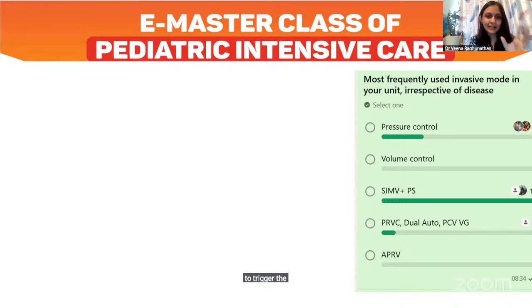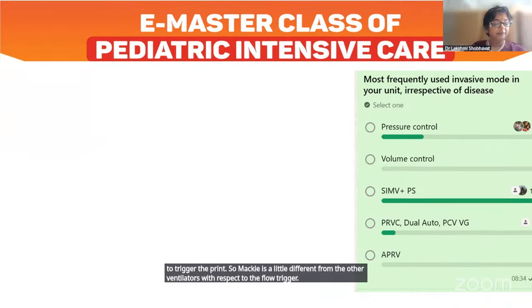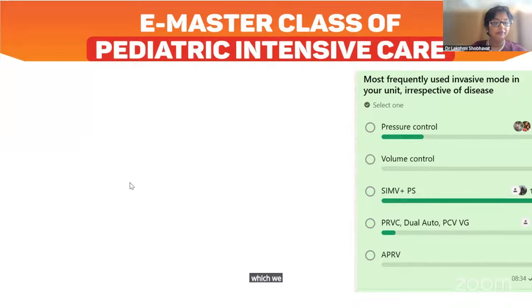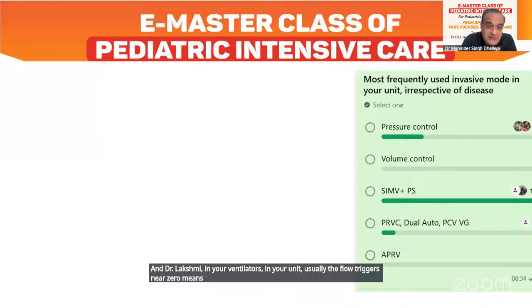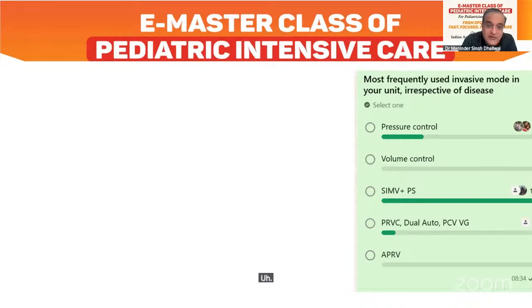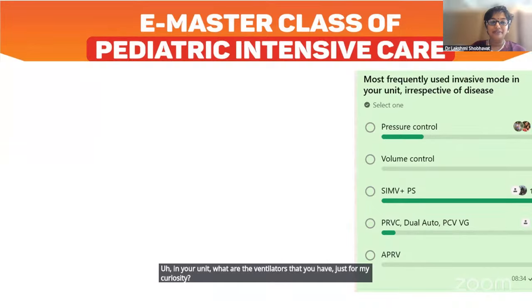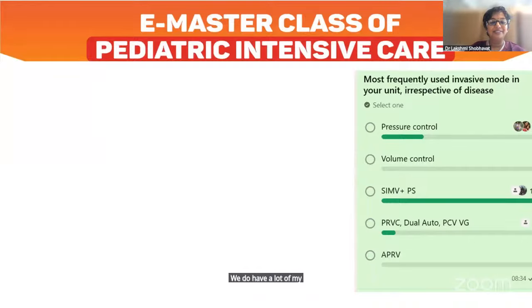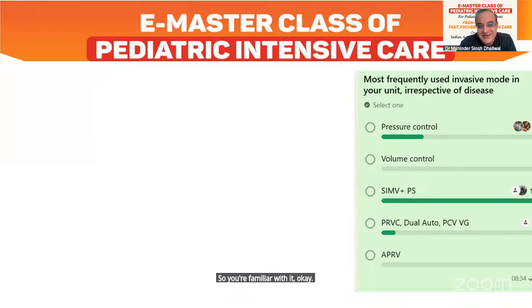So Maquet is a little different from the other ventilators with respect to the flow trigger which we set. And Dr. Lakshmi, in your unit, usually a flow trigger near 0 means very, very sensitive. What ventilators do you have in your unit, just for my curiosity? We do have a lot of Maquet, so we are familiar with it. Because they are different ventilators, the flow triggers are different.